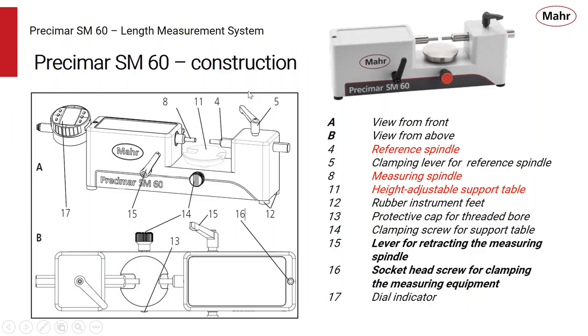Just want to point out a few of the important things about the construction. I mentioned the robust cast base of the system, and when you pick it up, you'll feel how robust and heavy it feels. So we have our reference contact here, which is clamped in place by a little handle. There's an adjustable reference table which can go up and down to make sure that your part is centered within the anvils. And then we have our sensitive contact, which is retracted by handles, one on each side. So, like I mentioned before, that handle is an over travel protection so that you can't damage the indicating device by pulling it too far back.